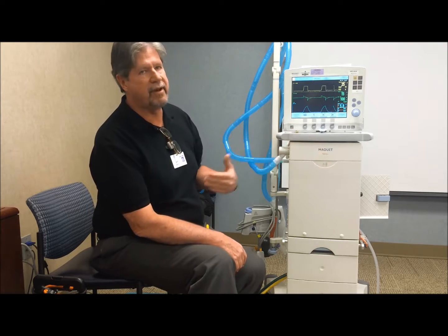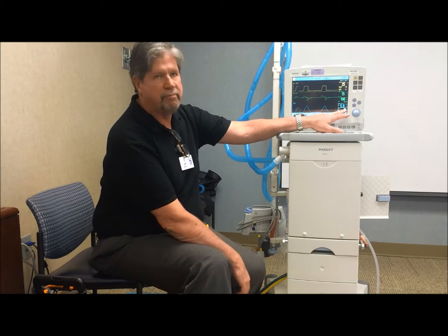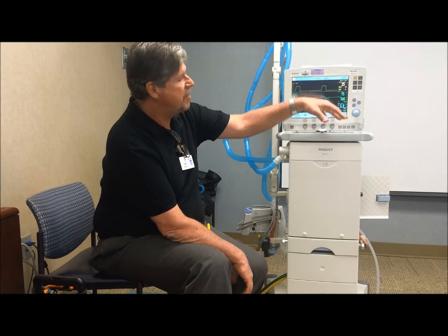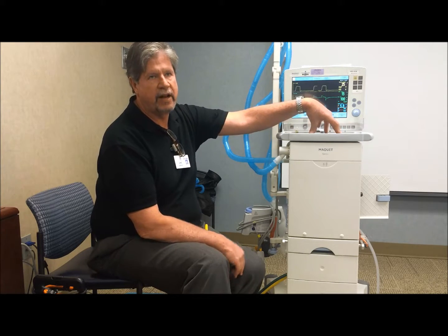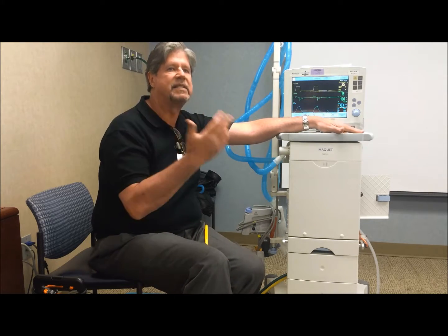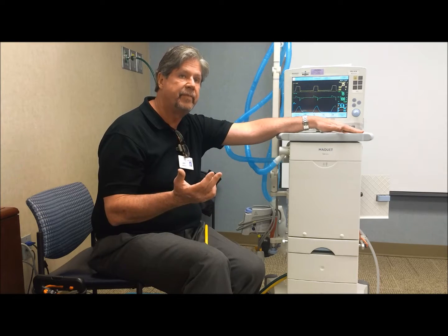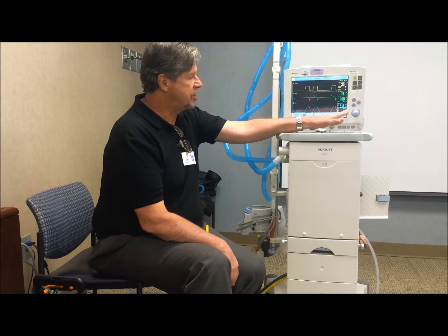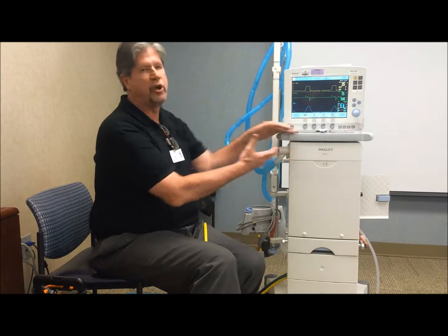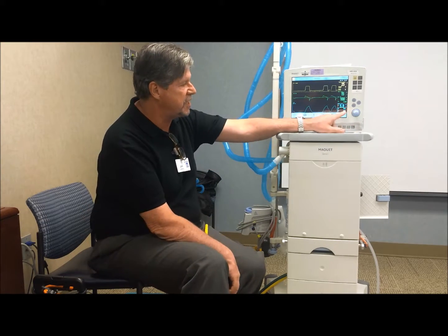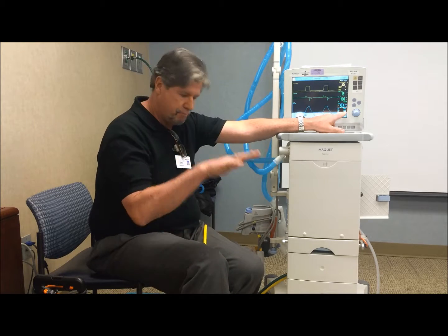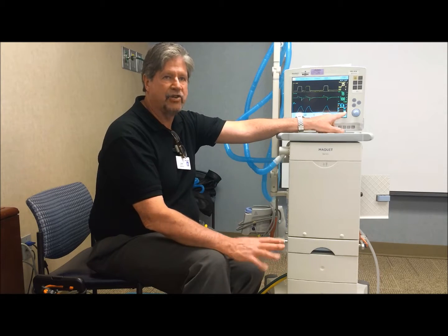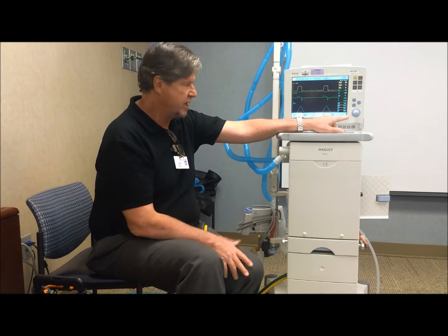Secondly, because of the different density, you're going to get volume fluctuations, because the measurement system in any one particular ventilator is designed to measure the density of O2 and nitrogen, which is a certain density, not O2 and helium. So as a result, even though there are no leaks, what you would generally see is your exhaled tidal volume being lower than what is actually being delivered to your patient.